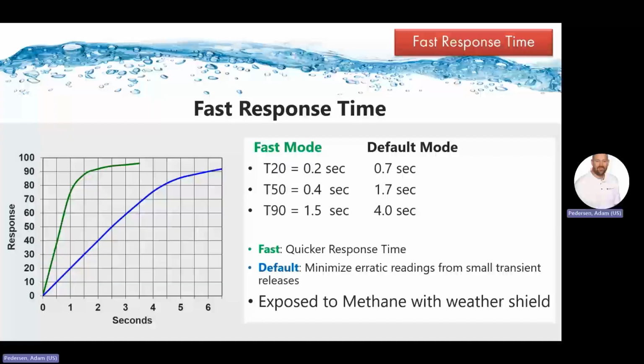A little bit about those response times. The user has the option to select the response curve they like using a HART device. The default mode at T20 has a response time of 0.7 seconds, 1.7 seconds at T50, and 4 seconds at T90. The default mode minimizes nuisance alarms from small transient releases, where the fast mode is going to give you faster response times. And so again, the user can choose which mode they want with that HART device.